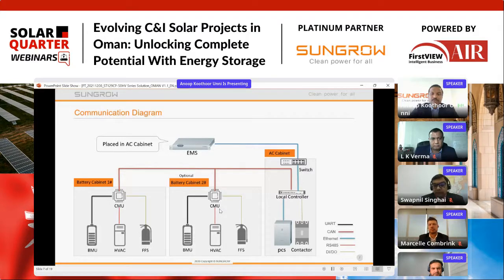For example, if you are going to connect 2 battery banks with one PCS, the first battery bank will have a battery management unit and HVAC and firefighting systems. All the communications loop into the common monitoring unit, and from there it connects to the local controller. Similarly, battery cabinet 2 also connects to the local controller. Once all the signals reach the local controller, it has an additional switch where the EMS is integrated, and the EMS can further communicate with any other similar communication protocol. So this is a simplified solution of the communication diagram.